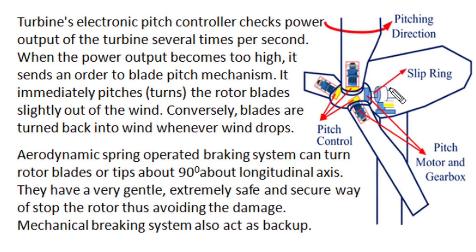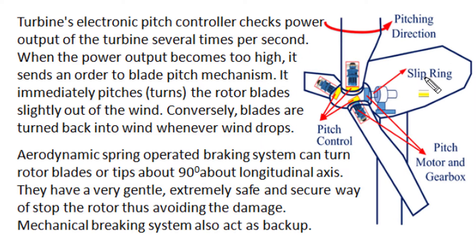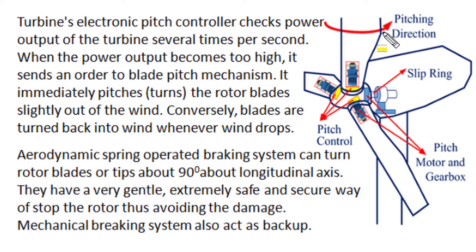Although the modern doubly-fed induction generator can maintain grid connectivity irrespective of variation in wind velocities or turbine rotation, all turbines also have automatic blade pitching control. When the anemometer sends wind velocity information to the electronic pitch controller, it checks the power output of the turbine. If the electrical output is too high, it sends an order to the blade pitch mechanism to turn blade orientation so that turbine rotational speed remains within rated conditions. Conversely, if output is decreasing, the automatic pitching control turns the blades back to increase mechanical output, maintaining operation within rated RPM conditions.